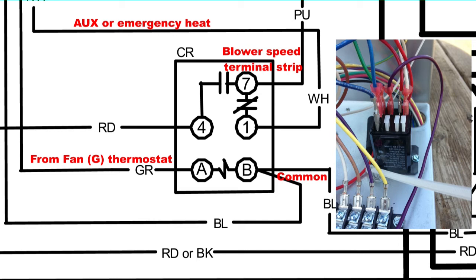It's 24 volts, an X13 motor. You would just select which tap and then that selection will run back to this number 7 terminal on the relay. We also have a number 4, and that is a hot 24 volts coming from the transformer. So everything on this particular relay is 24 volts—there's no high voltage.